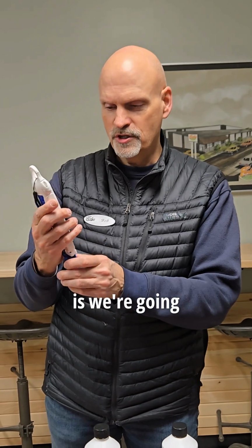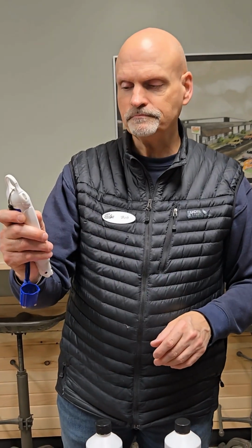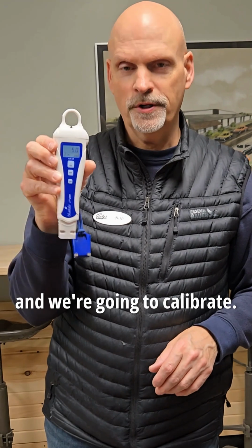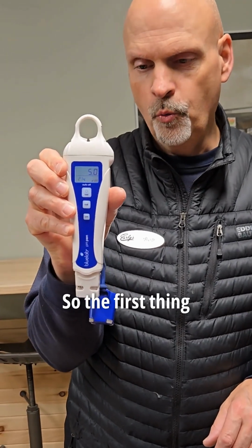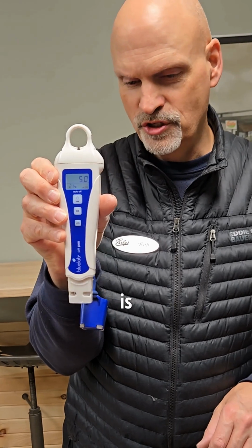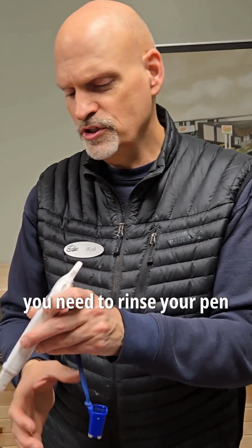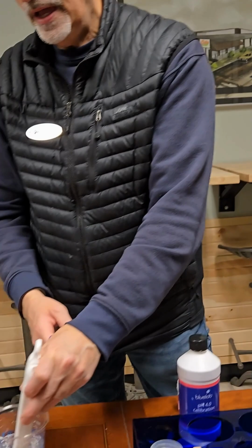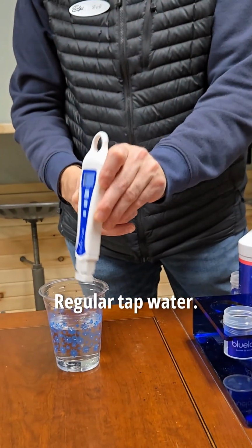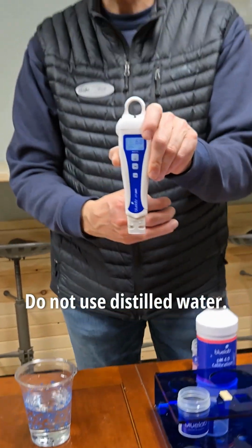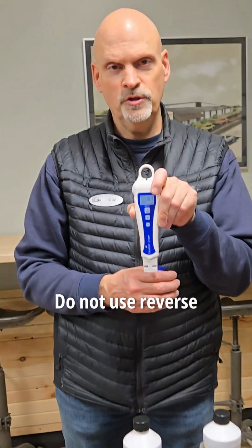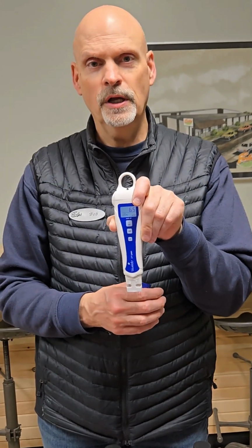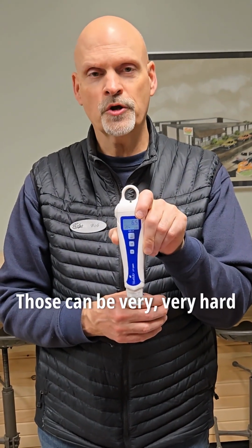Now what we're going to do is turn the pen on and calibrate. The first thing that you need to do is rinse your pen in a bit of regular tap water. Do not use distilled water. Do not use reverse osmosis water. Those can be very, very hard on a pen.